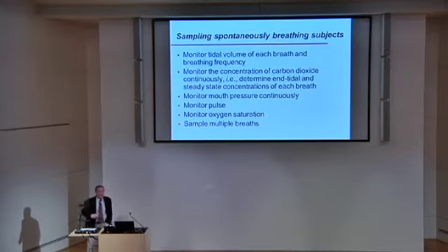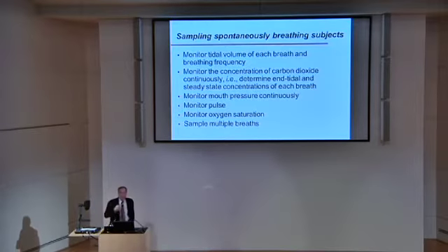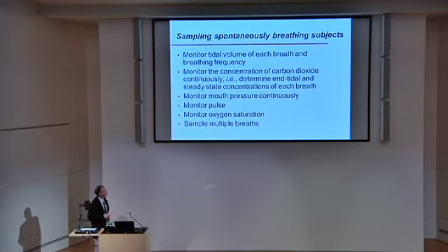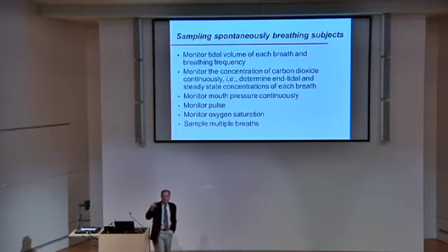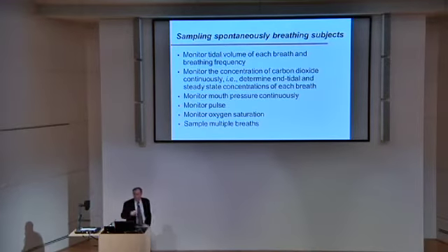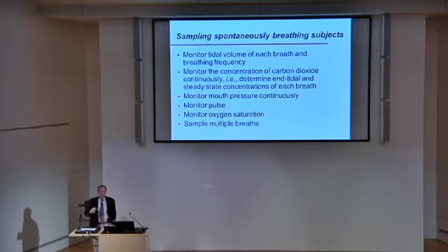So what you do is you try and monitor how a person breathes. And the way we did this, and this is the way that we probably set the stage for, is we monitor every tidal breath, the volume of the breath a person breathes. We monitor the concentration of carbon dioxide. We monitor the mouth pressure, because if you want to collect a breath sample, you want a person to breathe through a mouthpiece. And the only way you can get a pressure in the mouth is if you make a seal. And finally, we monitor pulse, because that's a good idea of heart rate.